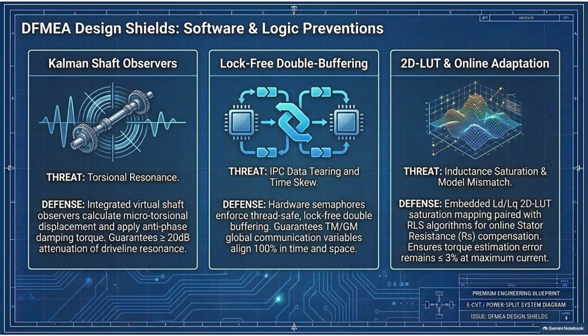So for the active damping lag, the torsional resonance, you can't wait for a physical sensor to report that the shaft is twisted. Because by the time the data is processed, you're already lagging. Exactly. So they implement Kalman shaft observers in the software. That's a concept from aerospace navigation, isn't it? It is. It's not just reacting to sensor data. It creates a high-fidelity, virtual kinematic model of the transmission that runs parallel to the physical hardware. Oh, wow. So it's calculating the twist of the metal before the sensor even feels it?